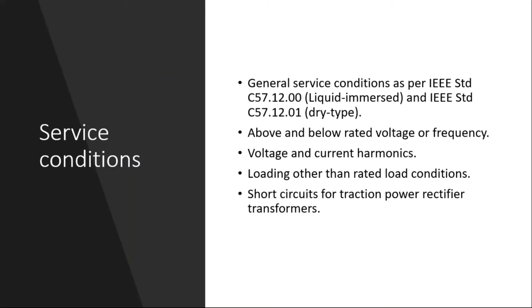General service conditions are covered in standard C57.12.00 for liquid immersed transformers and C57.12.01 for dry type transformers. For special application transformers, the same applies, and operating continuously above nameplate voltage under no load condition is 110%, and if it is loaded, the combination of voltage and frequency shall be limited to 105%, with the temperature limit as specified in the general standard for the core to meet.